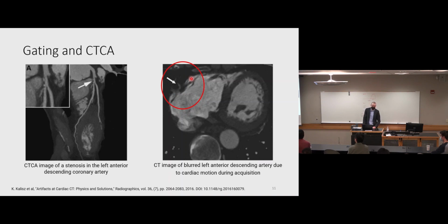One is called prospective gating with ECG. So the person can have ECG leads on them, they're lying down in the scanner. And then based on the electrical activity of the heart, it's possible to only turn on the X-ray tube, only acquire the images at the point in the heart where there's less motion, and we call that the quiescent phase or the quiescent period of the heart, okay? And so that can work, but unfortunately, even using that approach, about 20 to 30% of the scans end up being non-diagnostic and not being useful.